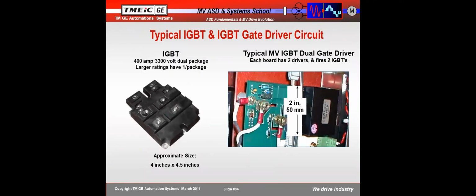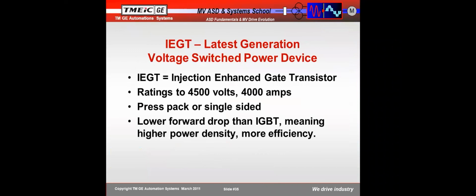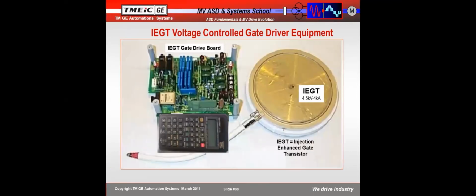This is an IGBT. If I looked at that, and nobody told me, I wouldn't know whether that was a low voltage or a medium voltage IGBT. They tend to look alike, but a tremendous development in drives that really revolutionized drive technology. This particular one is 400 amps and 3,300 volts. Now an IEGT is the latest generation. It can go up to 4,500 volts and 4,000 amps.